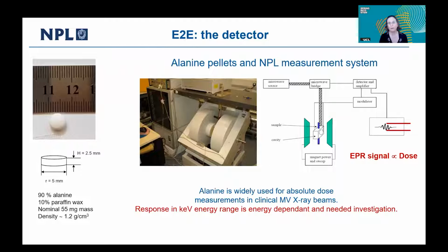We have already talked about the phantom, but every end-to-end test has a phantom and a detector. So now is the time to speak about the detector. Why did we choose alanine? Alanine is an amino acid that responds to irradiation by creating free radicals. The relative concentration of those radicals can be determined by electron paramagnetic resonance spectrometry, commonly known as EPR.